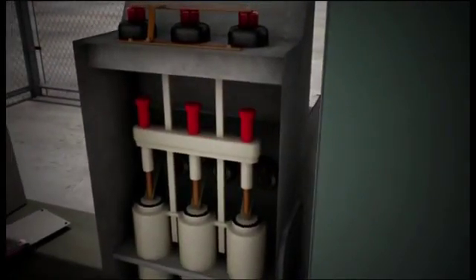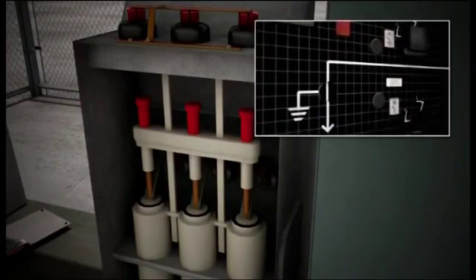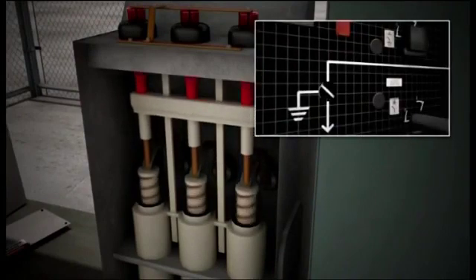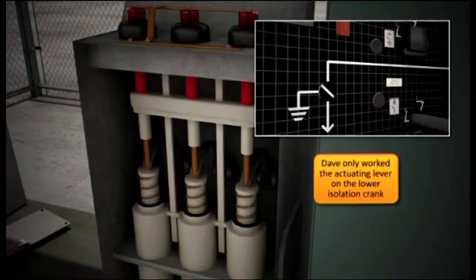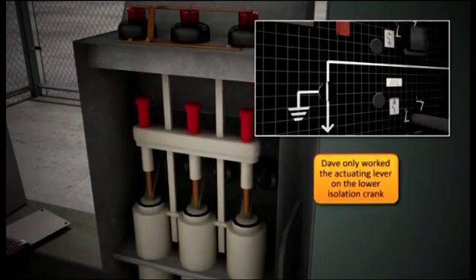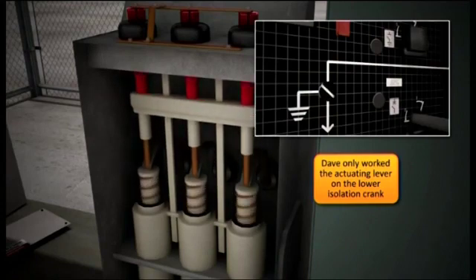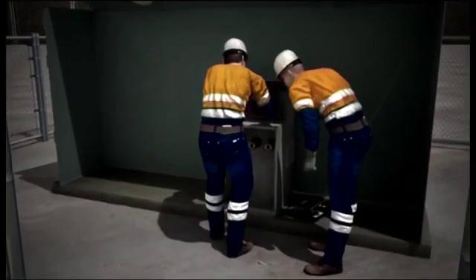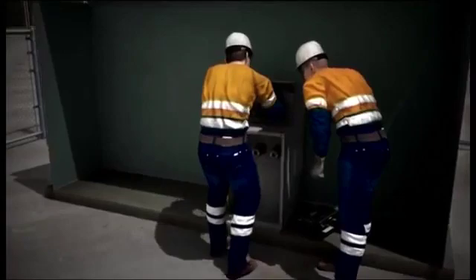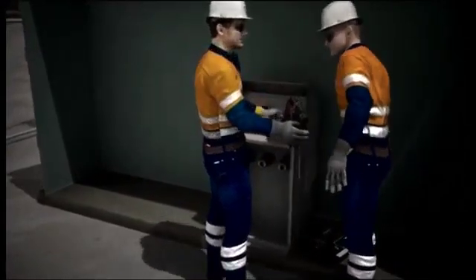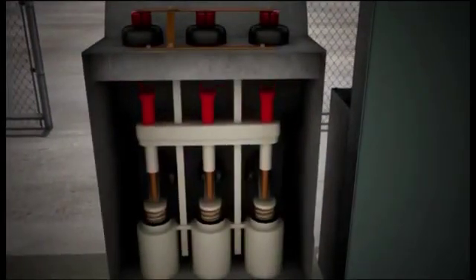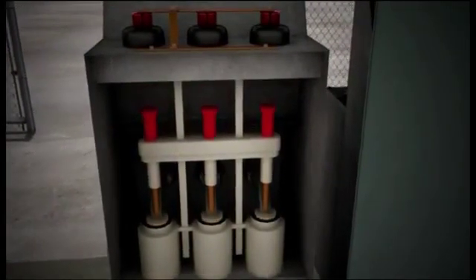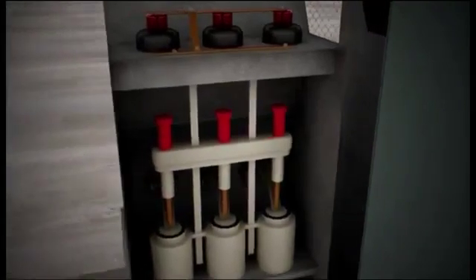Looking at the animation, we can see what happens when the actuating lever is cranked to de-energize the unit. Dave only worked the actuating lever on the lower isolation crank, causing the train to lift off the live ring main unit and sit in the middle, or open position, on its tracks. Once the switching mechanism was removed from the control shaft, there was nothing to hold the train in place, and gravity simply acted to pull it downwards, eventually remaking contact with the live 22 kV ring main.